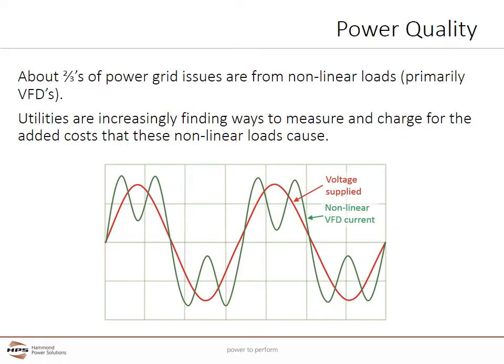Anything that rectifies AC to DC power is a non-linear load and produces current harmonics. The line side of a VFD is basically a DC power supply and is a classic three-phase non-linear load. Other large non-linear loads can include inductive heaters, arc furnaces, welders, and large DC power supplies and chargers. Overall, non-linear loads now make up the majority of all utility loads.